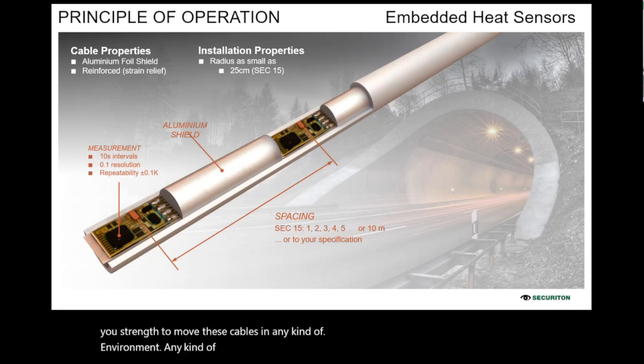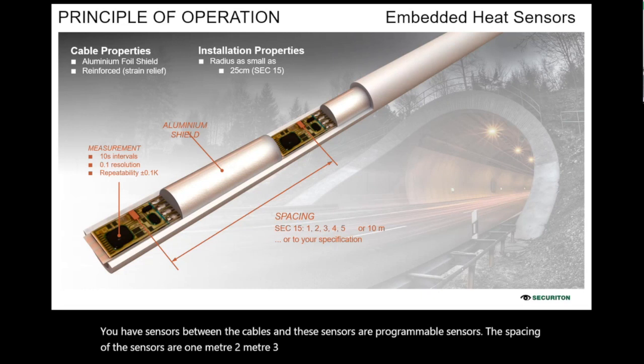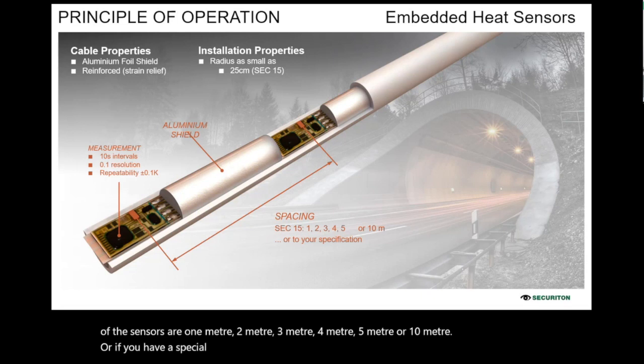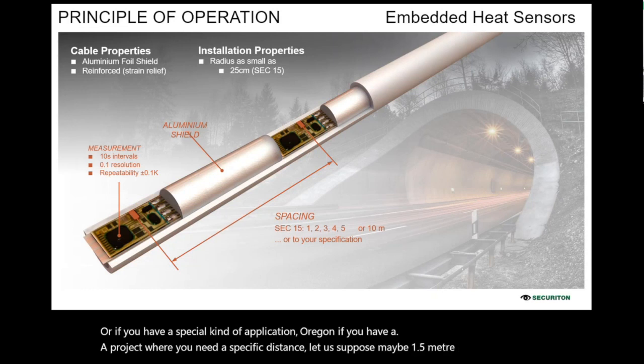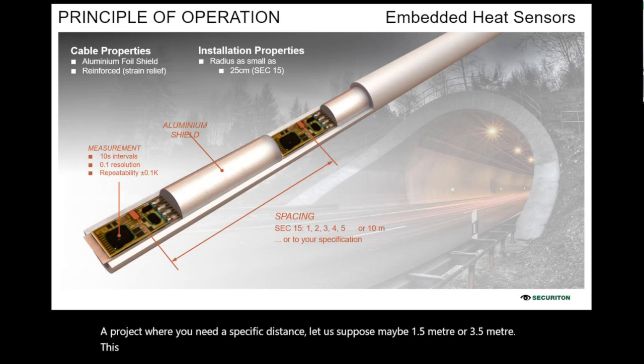You have sensors between the cables, and these sensors are programmable sensors. The spacing of the sensors is 1 meter, 2 meter, 3 meter, 4 meter, 5 meter, or 10 meter. Or if you have a special kind of application, or a project where you need a specific distance, let us suppose maybe 1.5 meter or 3.5 meter, this is also possible. We can make these cables as per your requirement also.